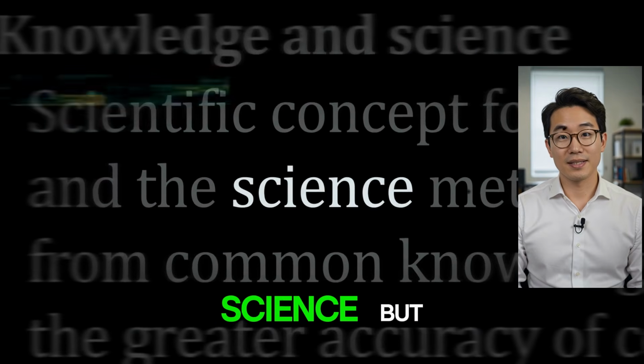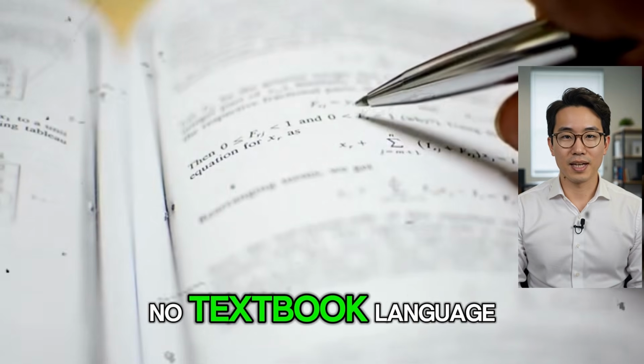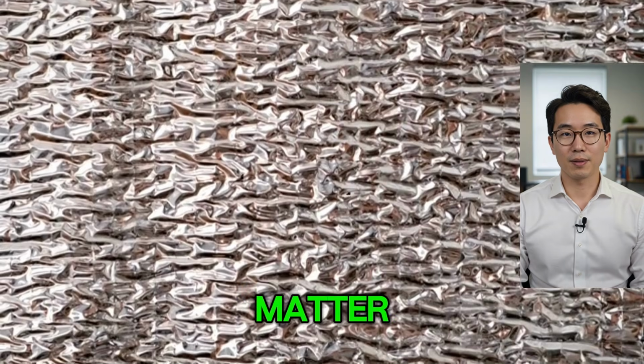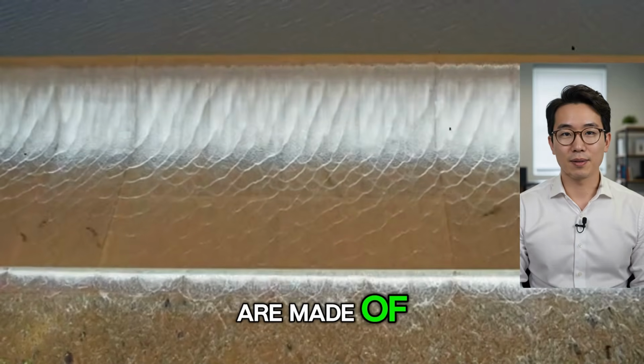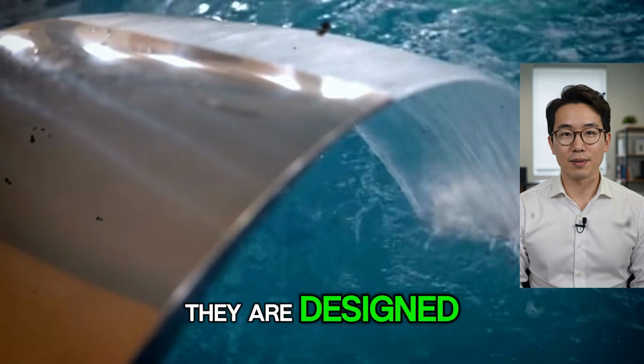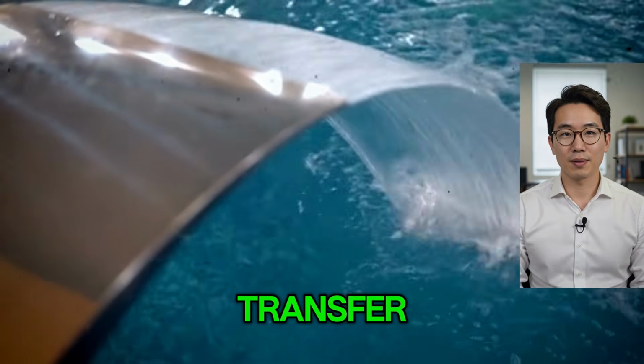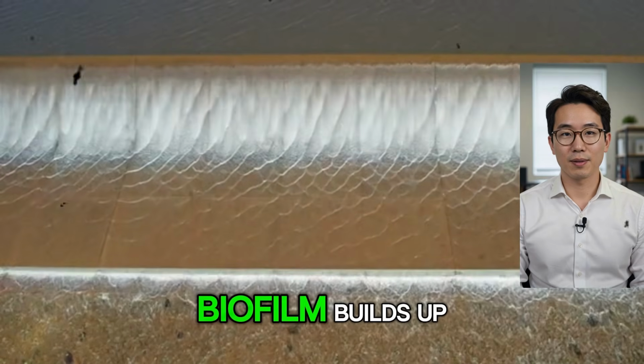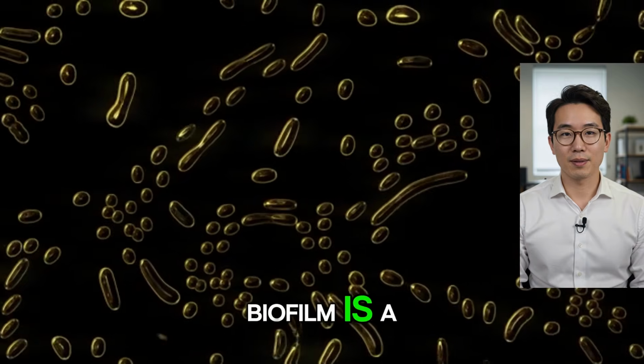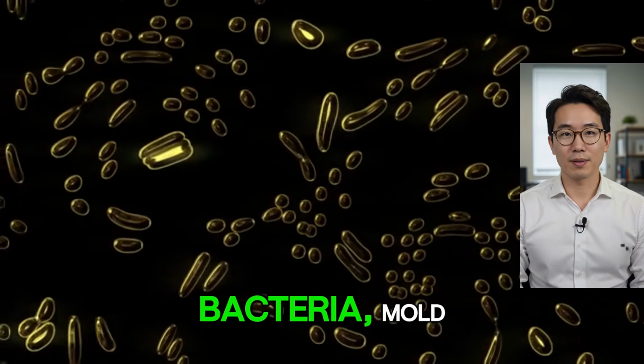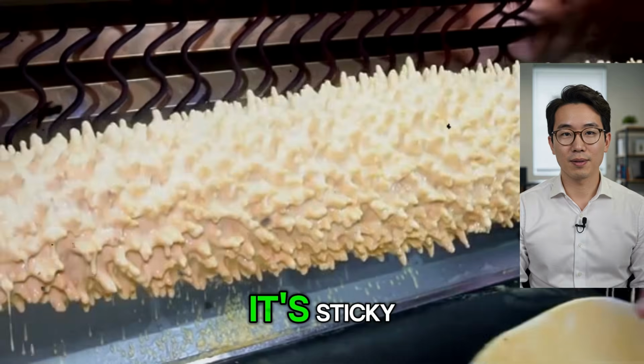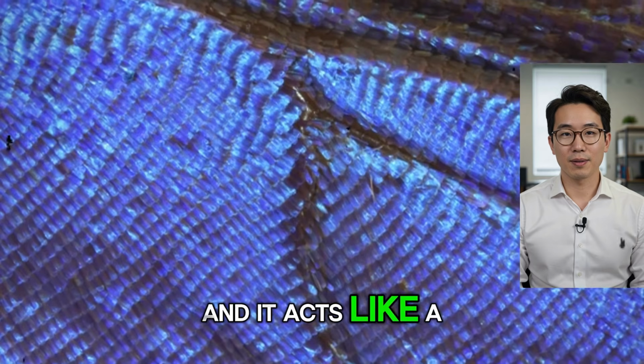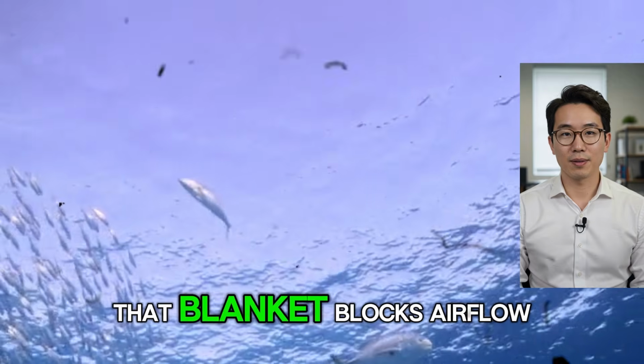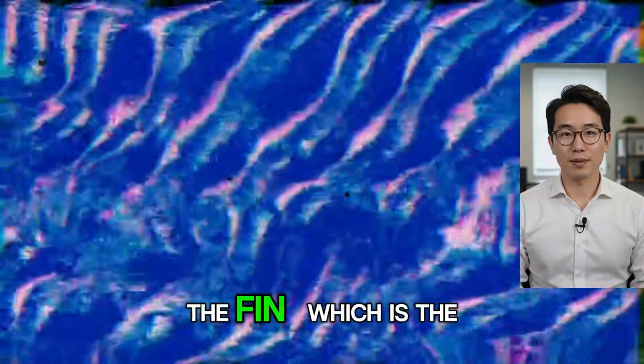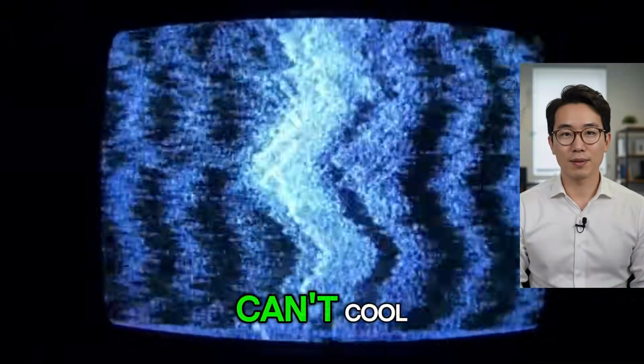Let me give you the science, but I'm going to keep it simple. No textbook language, just the facts that matter. Your AC coil fins are made of aluminum or copper. They are designed to allow maximum airflow and heat transfer. But over time, a biofilm builds up on these fins. Biofilm is a combination of dust, bacteria, mold spores, and organic grease. It's sticky, it's dense, and it acts like a blanket around each fin, and that blanket blocks airflow. It also insulates the fin, which is the exact opposite of what you want. A fin that can't breathe can't cool.